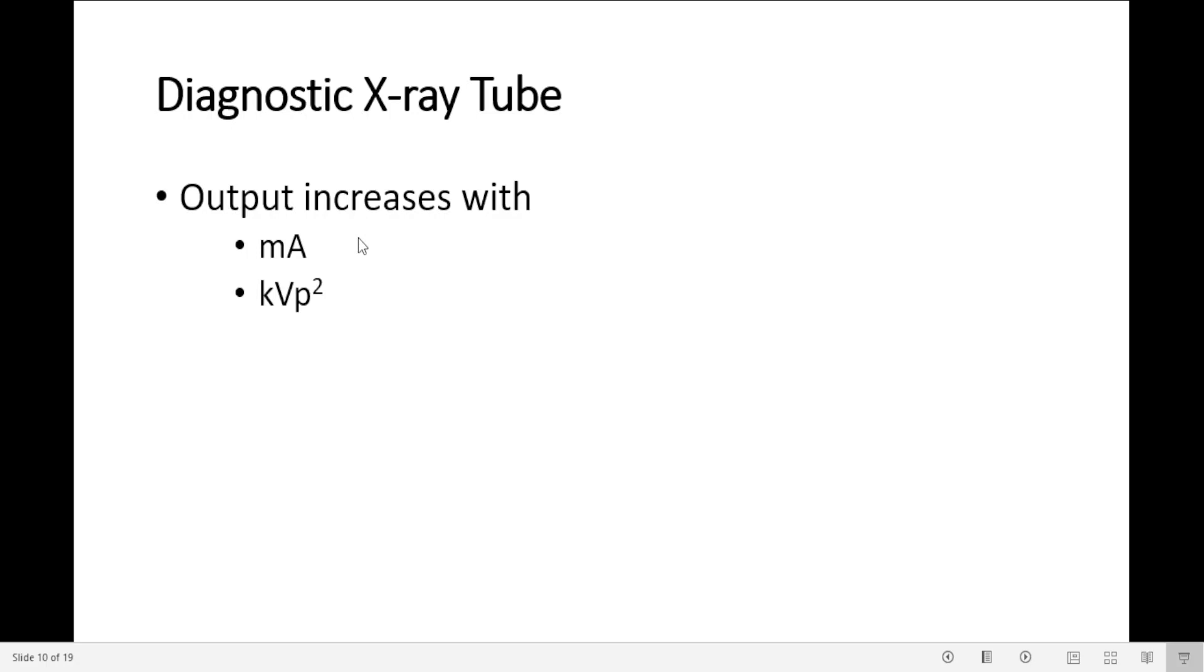Output increases proportionally with the tube current in mA and approximately with the square of the tube voltage. If it is proportional to mA, if we double mA, we are going to double x-ray production. It is approximately proportional with the square of the tube voltage with kVp squared. If we double kVp, we quadruple the x-ray production because we are dealing with kVp squared here.